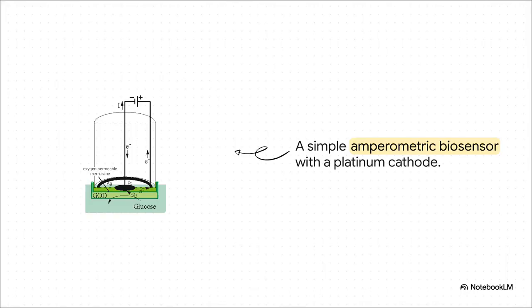Looking at the anatomy of that very first biosensor, it works by applying a negative 0.7 volt potential between a central platinum cathode and a surrounding silver anode. The biological sample sits on the outside. When you apply that voltage, the current is carried between the electrodes by a saturated potassium chloride solution.